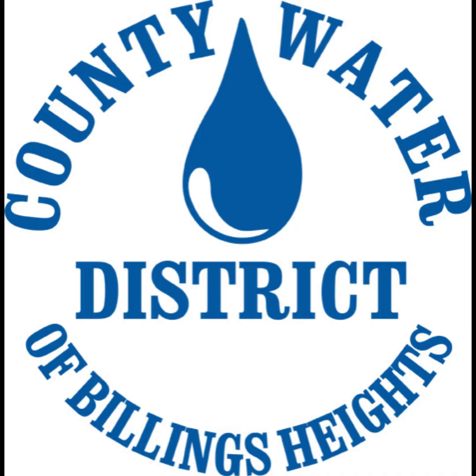All right, thank you, Brad. Yeah. So first I'll go over some background information. The Department of Environmental Quality, or the DEQ, sets regulations for Montana water systems. Pressures in the distribution system cannot fall below 35 pounds per square inch, or PSI, during the average day demand. During the peak hour demand while fighting a fire, the pressures can't fall below 20 PSI. Why is this a concern? Because when pressures drop below 20 PSI, there's a risk of contamination into the system.